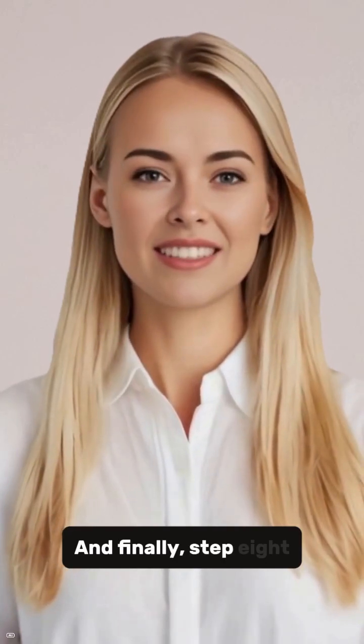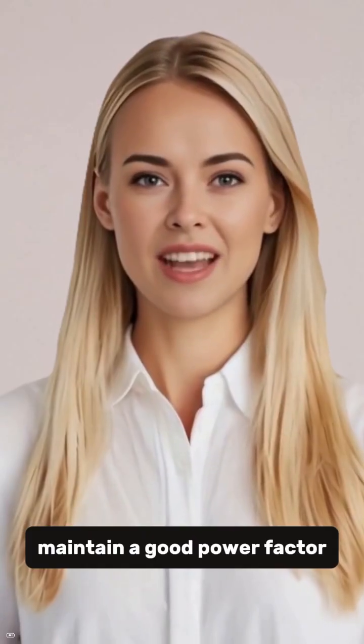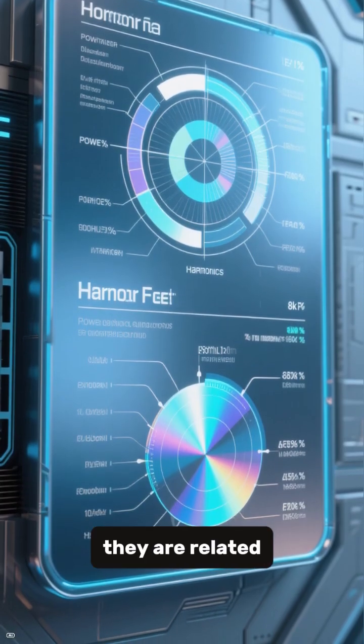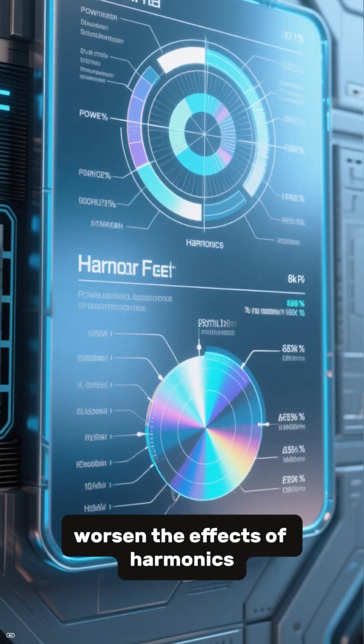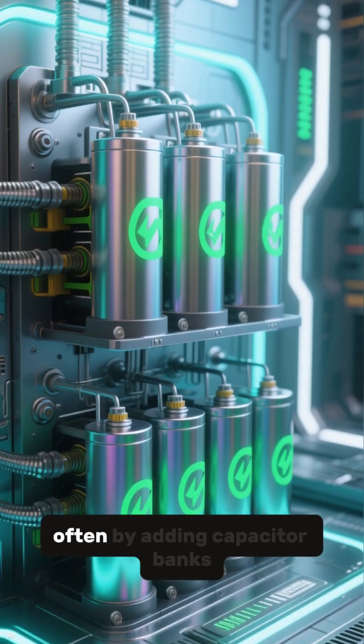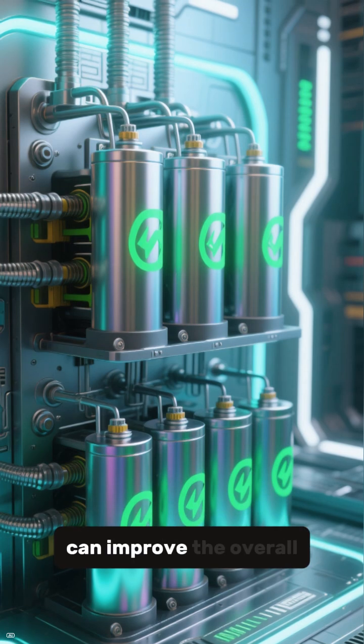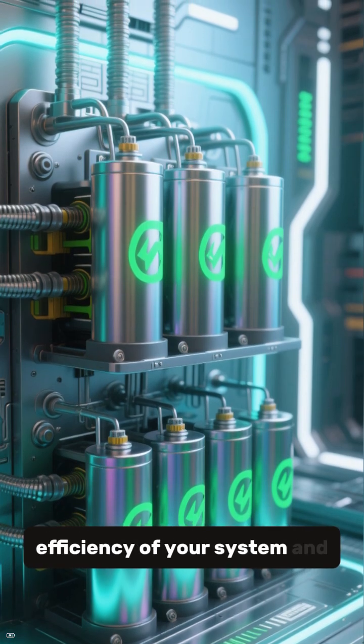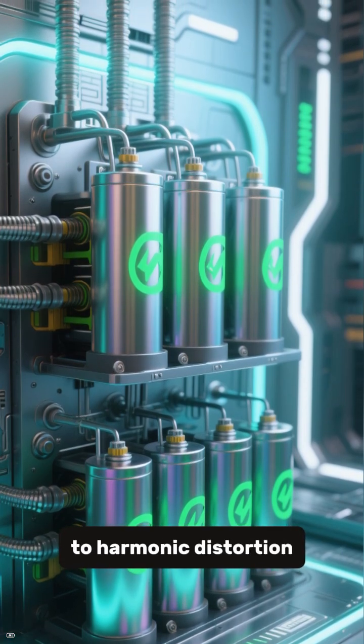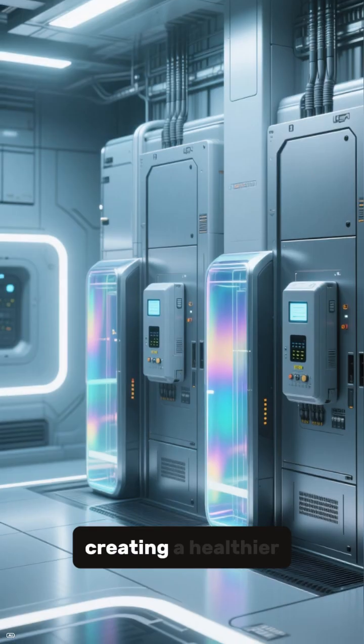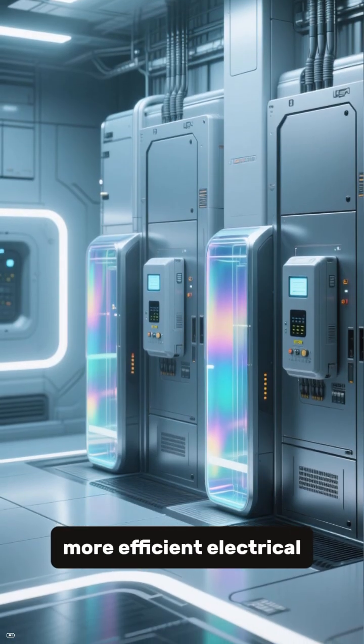And finally, Step 8. Maintain a good power factor. While power factor and harmonics are different issues, they are related. Poor power factor can worsen the effects of harmonics. Improving your power factor, often by adding capacitor banks, can improve the overall efficiency of your system and make it more resilient to harmonic distortion. It's all about creating a healthier, more efficient electrical environment.